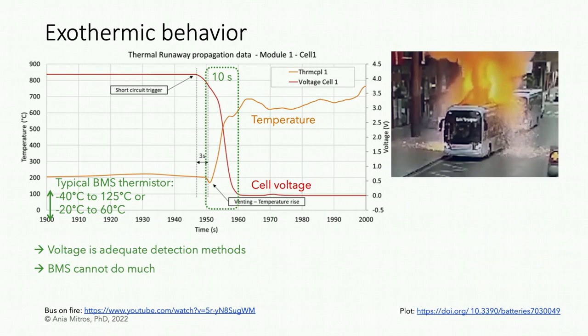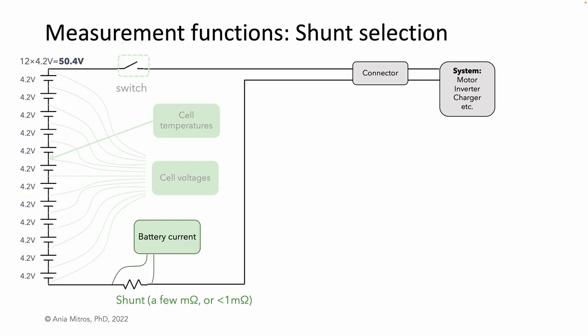It's too late to stop whatever caused thermal runaway. We can open the battery switch and disconnect the battery from the rest of the system, but that doesn't stop a fire inside the battery. And if we want to alert the user that the system has suffered a very major fault, voltage provides a faster warning that something is very wrong.